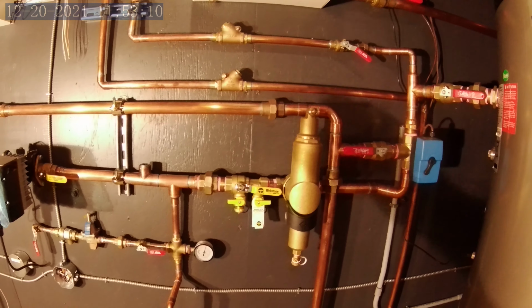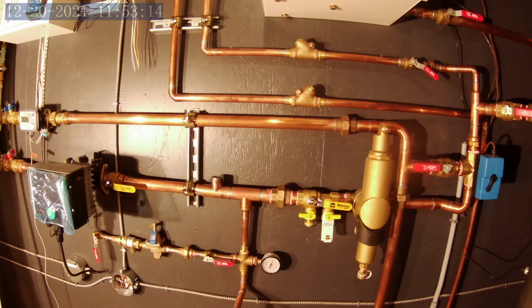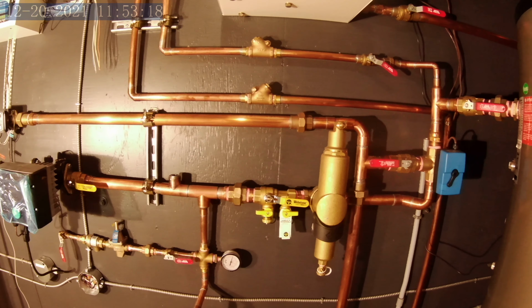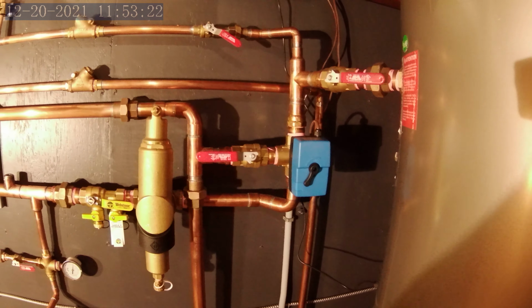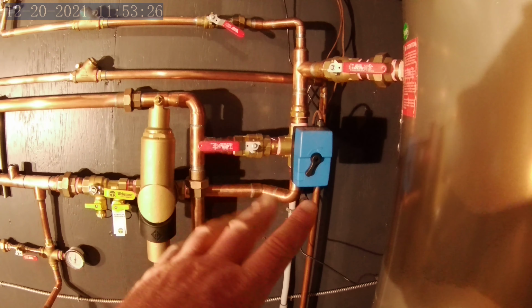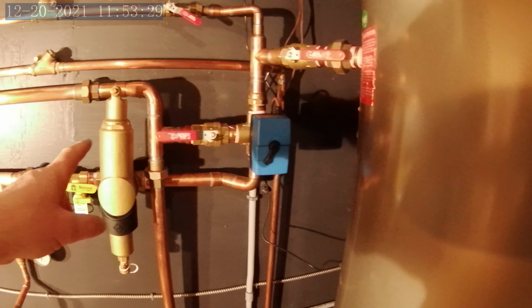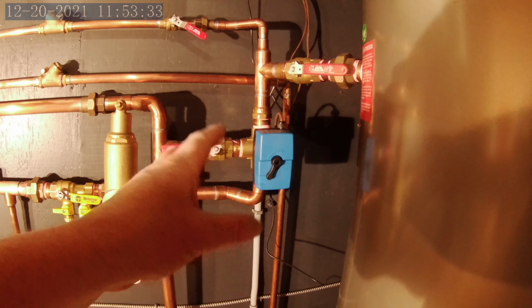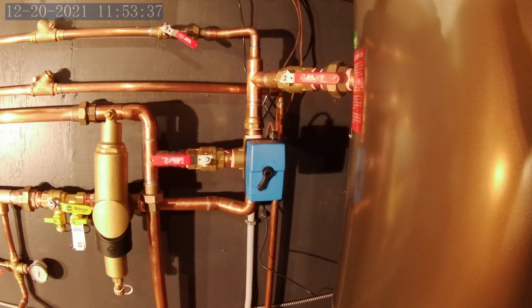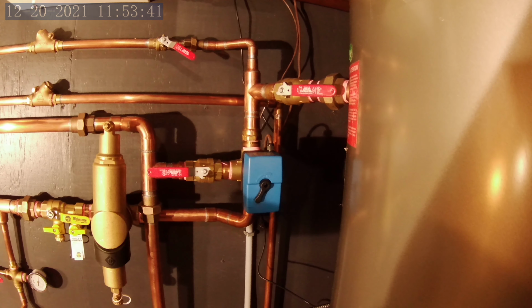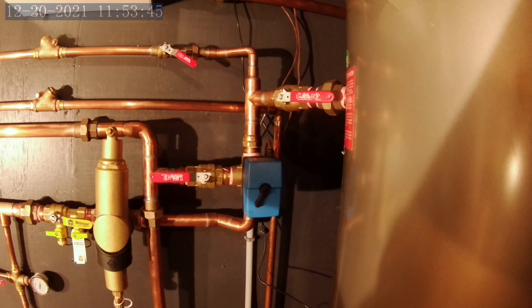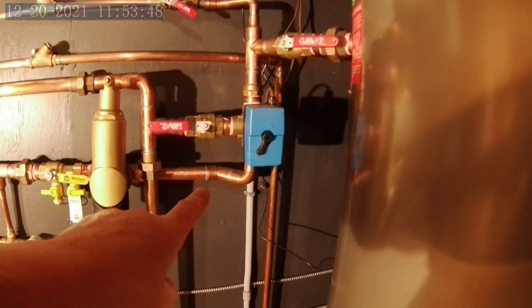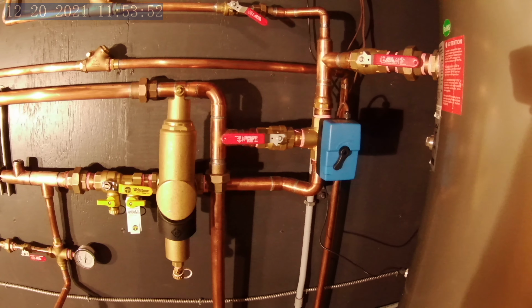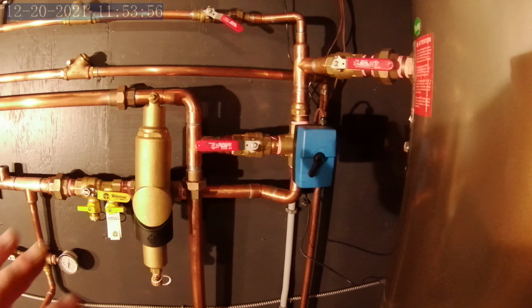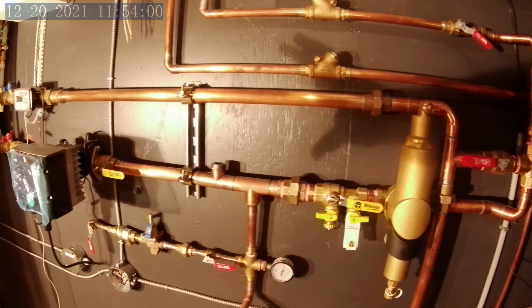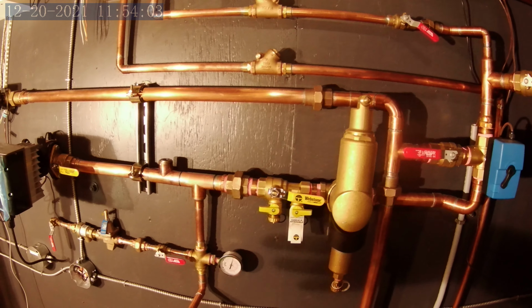Most of this copper will be left exposed because it will be at the panel required temperatures. During the summertime, when we're cooling, again, the water coming back now is warmer than the water going out, where this will become a chilled water tank. And so the warmer water will warm up the cold water, so that using the indoor RH sensors, we will be able to determine the dew point of the interior air and make sure that the water going out to the panels is at least a couple of degrees warmer than the dew point, so we don't have condensation on any surfaces. As a result, I don't have to worry about any of the feed piping to the panels, because it's always going to be above the dew point, so I don't have to worry about condensation.